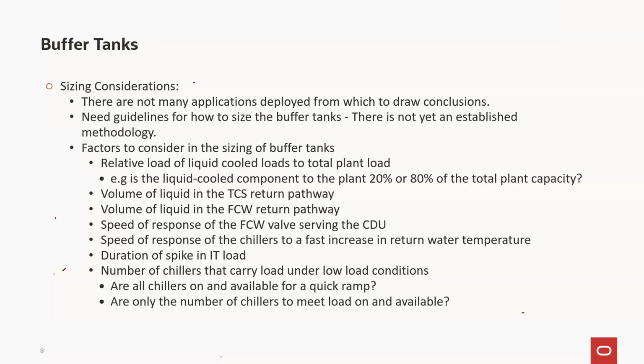Yeah, essentially, you just took my point. I wanted to turn this into a pitch for chiller-free primary side loops, because as you mentioned, then you don't have this issue. And I think we should not give up on convincing all the vendors to keep this in mind when they design their upcoming processors, GPUs, etc. On the other hand, if you're going chiller-free, you typically work with lower delta Ts, because you want a lower gap between outside temperature and your facility inlet. That means you typically have higher volume flow rates, so the flow rate on the primary side will be higher. The total volume of water on the primary side, if you design it, will actually be higher. So you get additional, intrinsic capacity because you have more water in your primary side anyway, which helps you. But as you said, it doesn't eliminate the problem entirely.